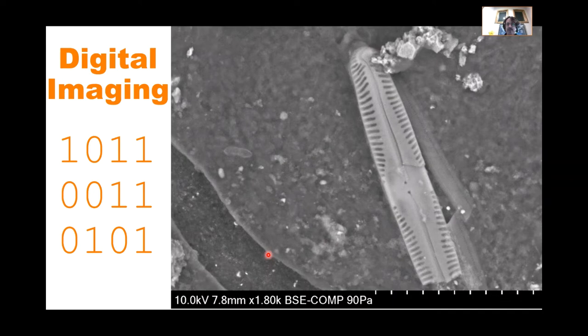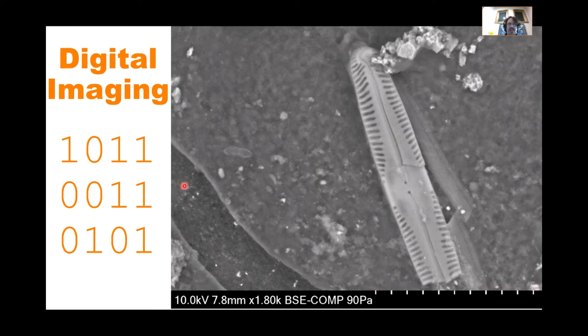What can make this micrograph better? The contrast is actually pretty good, but we have a dimensional reference bar without being told what distance it corresponds to. This is a Hitachi SEM, and nearly every Hitachi SEM gives a bar at the bottom as your dimensional reference. A number telling us what that distance means would make this a lot more useful — otherwise it's just a pretty picture.